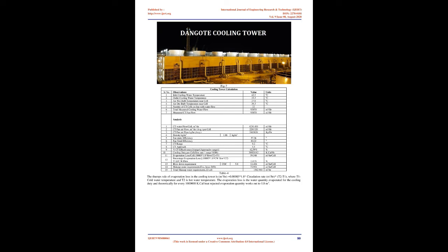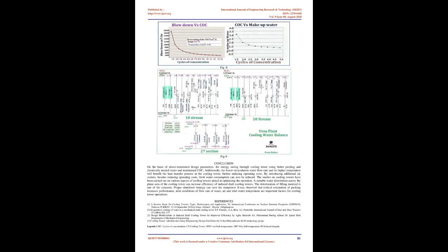The following variations from the design conditions are permissible. 1. Wet bulb temperature was not more than 8.3 degrees Celsius above or below design wet bulb temperature. 2. Range not more than 20% below or above, as per figure No. 6. 3. The circulating water flow was not more than 10% above or below the design circulating water flow. In the case of a multi-cell tower, it is permissible to shut down one or more cells. 4. The water was distributed to all operating cells and/or parts of the tower as recommended by M/S Paharpur. 5. The total dissolved solids in the circulating water, as determined by evaporation, were not exceeding 5000 ppm.